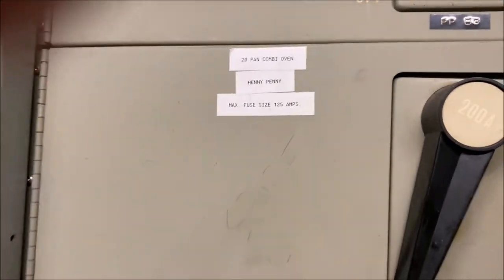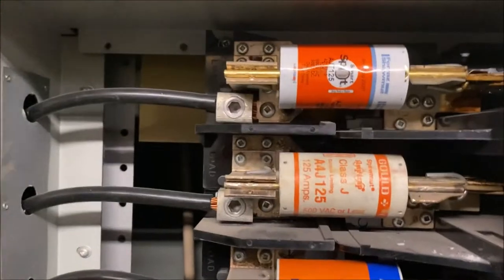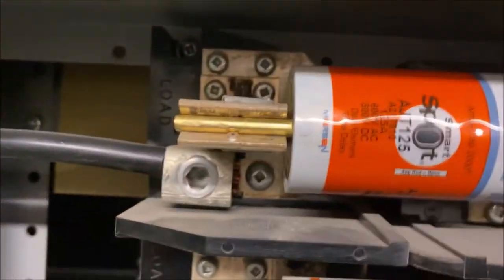I just want to go in here and see which fuse they changed. Looks like it's this top one here, so L1. Based on the other service calls prior, L1 was the one that was definitely blowing.